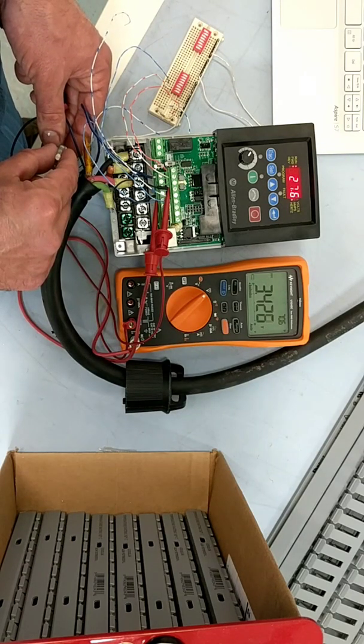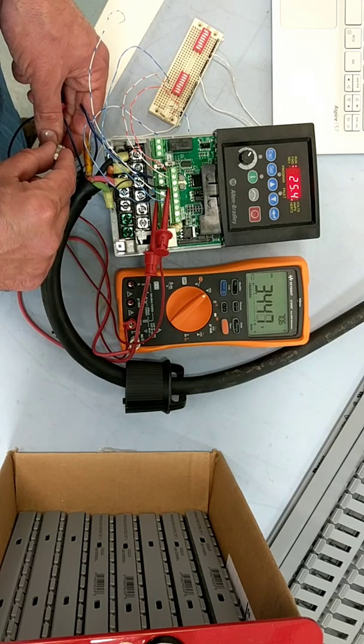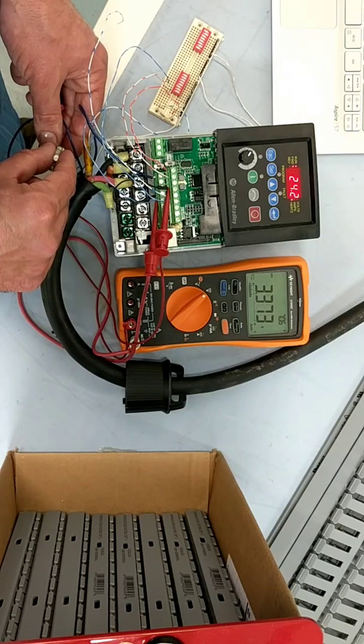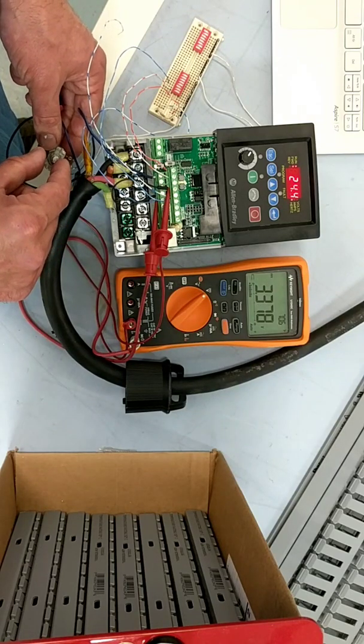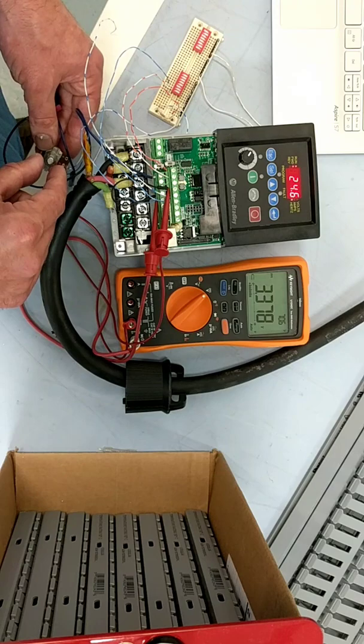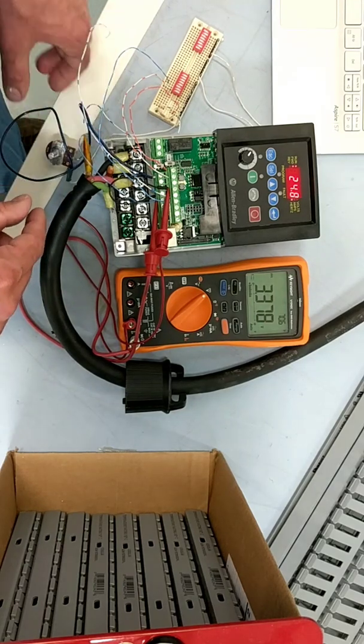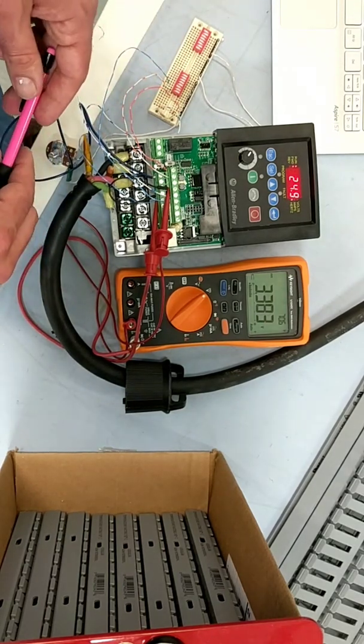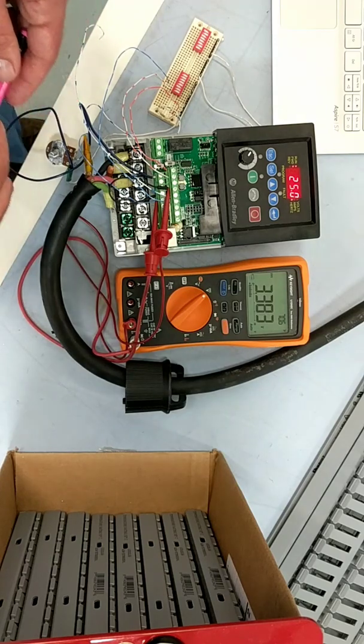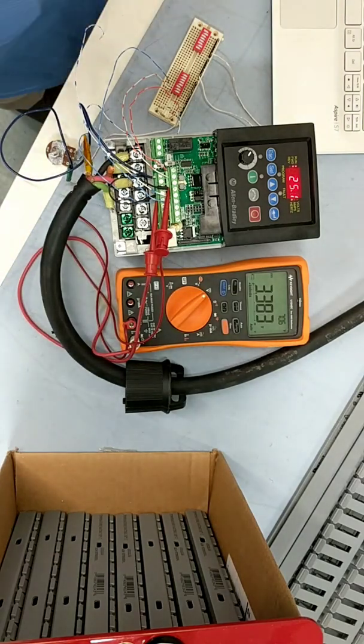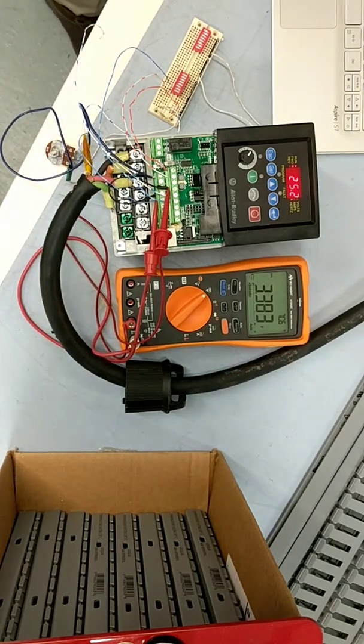Having some problems finding that dead zone, but we can see that the frequency is moving very, very slowly here, right around 3.4. Excellent. So that's how you set up a PowerFlex 40 VFD. Let's power cycle, make sure our settings are stuck.